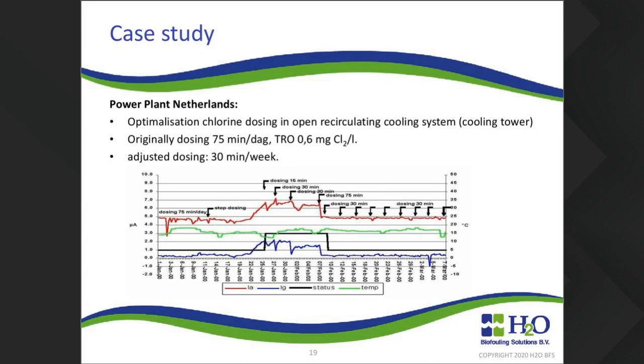So the 75 minutes per day were sufficient to prevent the biofilm buildup. So we stopped the dosing and we increased the biofilm on the probe. And then we started to dose different time intervals. And after some examples, we noted that a 30-minute dosing per week for this location was already sufficient to prevent biofilm buildup. So instead of dosing 75 minutes per day, we switched to 30 minutes per week. We were able to control biofilm buildup in this specific cooling tower.